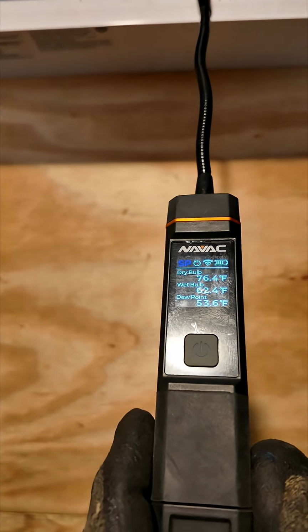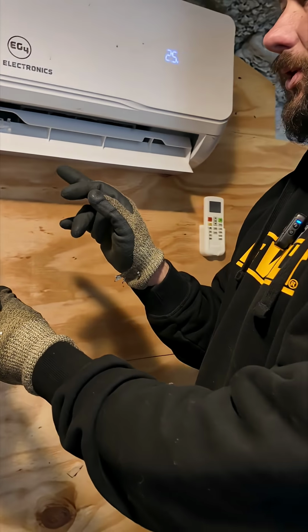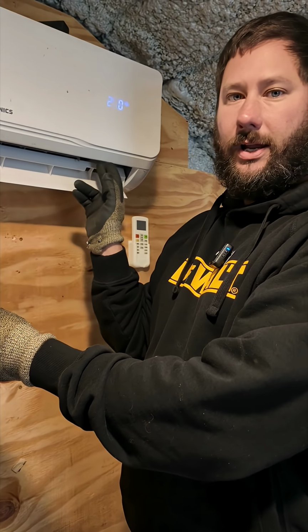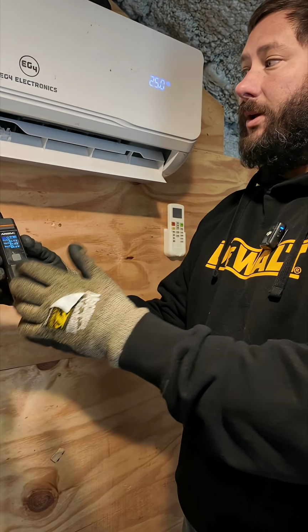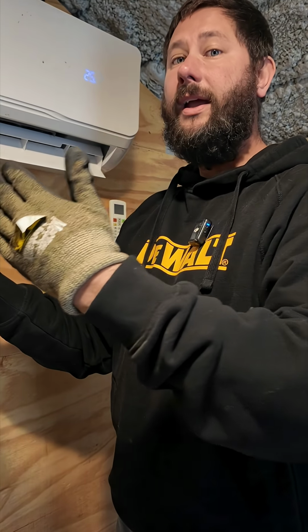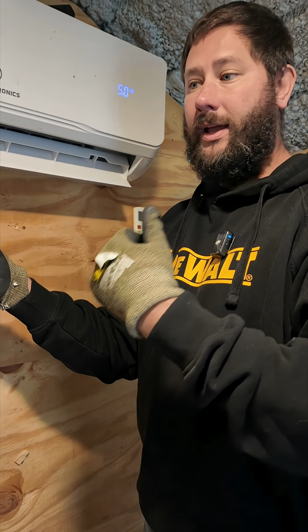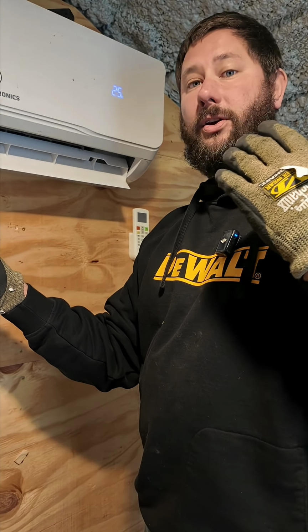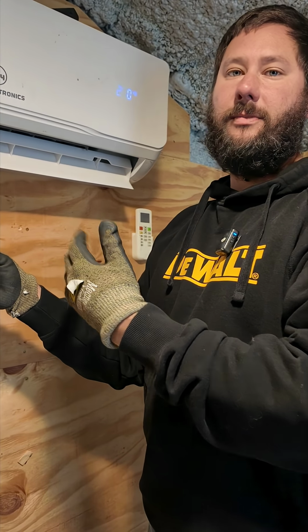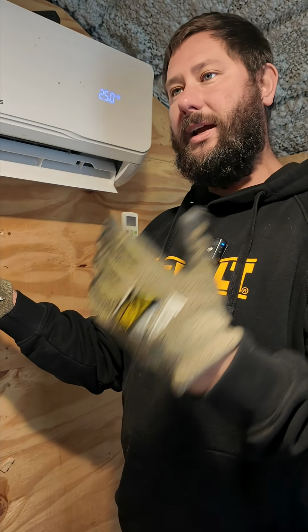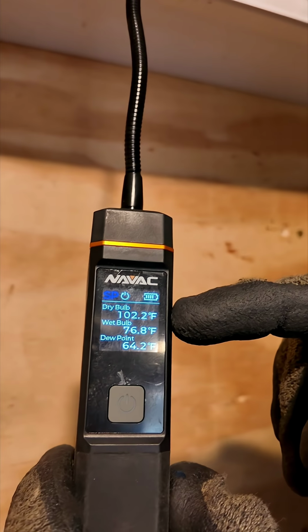temperature. Now be careful. You don't want to put the probe too far into the unit right here where the vane opens and closes, because if you stick it too far in, it's going to hit the blower wheel and you're going to break the blower wheel, and then you're going to have no performance out of your mini split because it's broken now and you got to order a part. So don't do that.